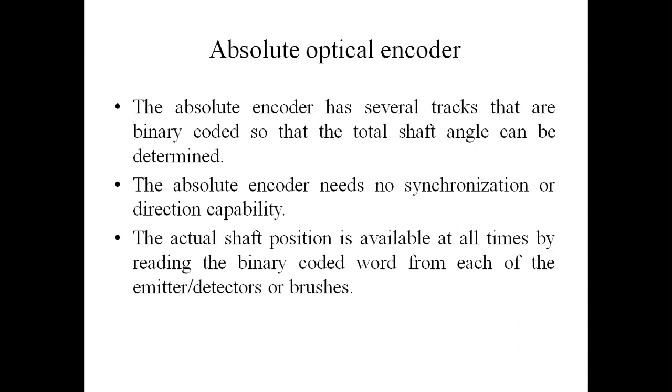When a disk with the pattern rotates, the light passing through the slits is transmitted or blocked according to the pattern. The received light is converted into an electrical current. The detector elements take the form of waves and become a digital signal. This type of encoder outputs the rotation angle in parallel as an absolute value in the encoded code.